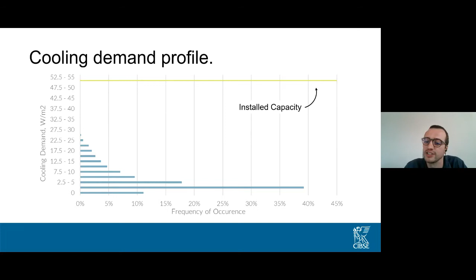Here's another example of the kind of information we want to recover: a chart showing the cooling demand profile of a shopping centre in London. For about 75% of the year, the cooling load was less than about 5 watts per metre squared, tapering off to a peak measured load of about 30. What's interesting is that yellow line is the installed capacity of the cooling system. Do you think a cooling system sized for that capacity is necessarily designed to operate efficiently at the low loads the building is generally operating at?